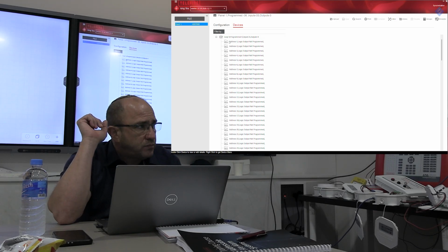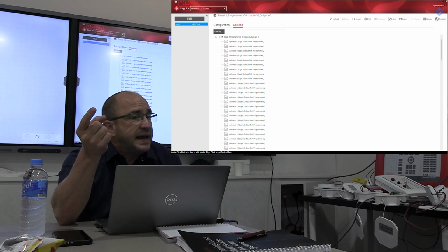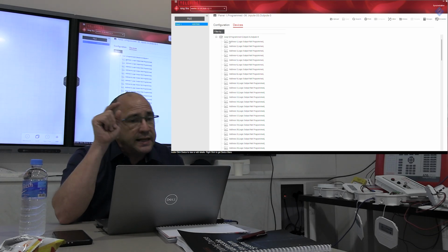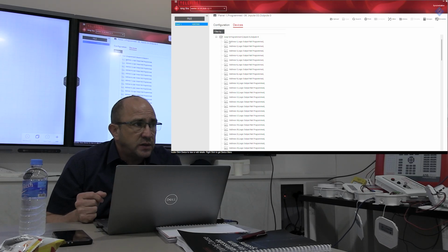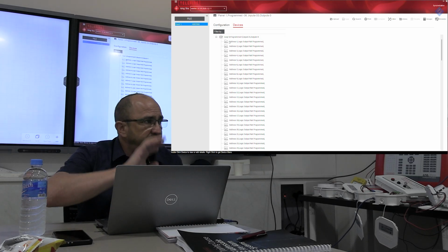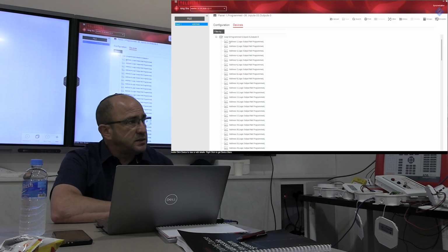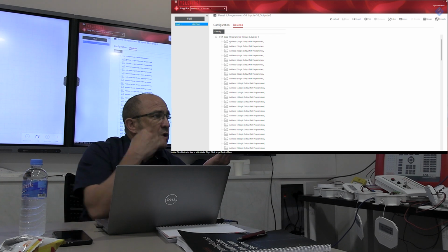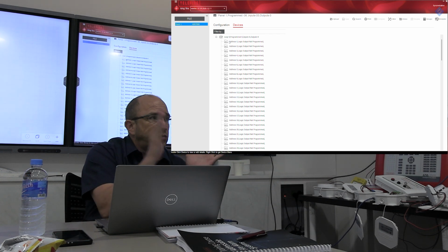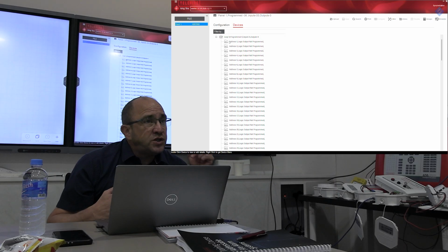It can be from floor 1 and floor 2, or only from floor 1, or only from floor 2, 2 detectors. Not only that, also push buttons. Either 2 push buttons or 1 push button and 1 detector, but the terms are 2. But if there's a flow switch, straight away.